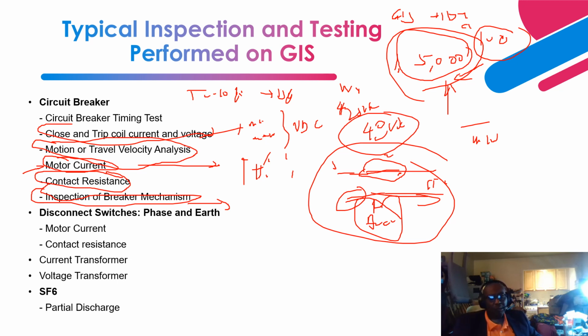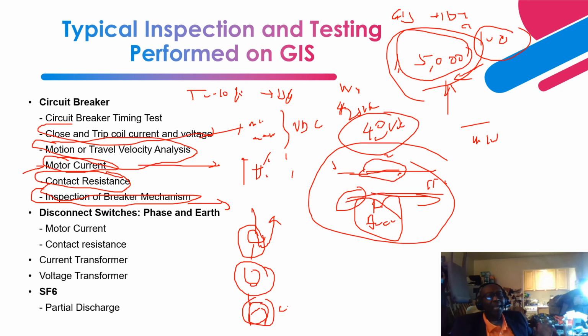Next is disconnect switches, right? As you know, you have a breaker, and on each side of the breaker, definitely you're going to have a disconnect switch. Because once you interrupt the breaker, there's going to be capacitively coupled charges. Once you open the circuit breaker, then you can operate the disconnect switch, because this is a no-load operating disconnect switch, but it has a certain capacitive current that it can break, let's say about 0.5 amps. So that's when you open it to isolate the side and the side.